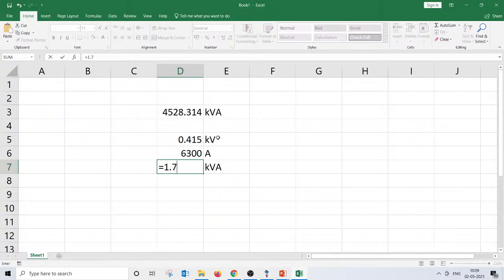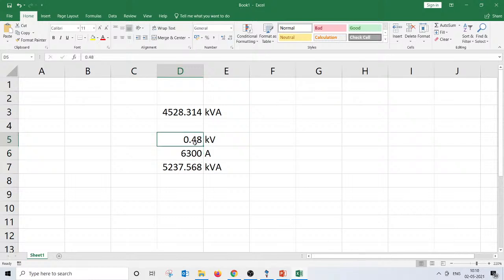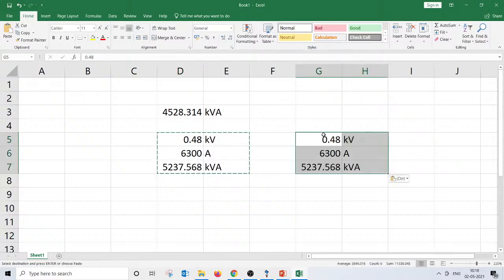So the limitation on the transformer rating, if it is connected to 415 volt, is about 4500 kVA. If it is 0.4 kV, it is about 4.3 MVA. If it is 380 volt, then it is further less. If you have 480 volt, then it could be slightly more, right? So this decides basically what would be the maximum transformer rating which can be connected at the low voltage side. So let's move on to the next topic.